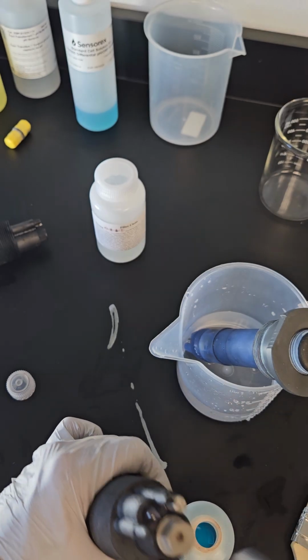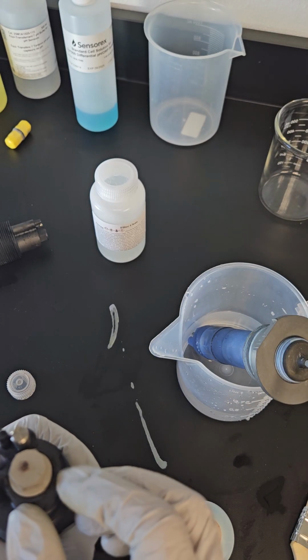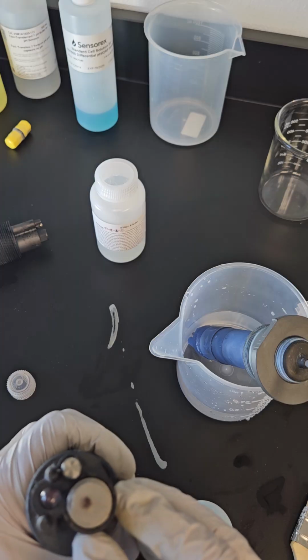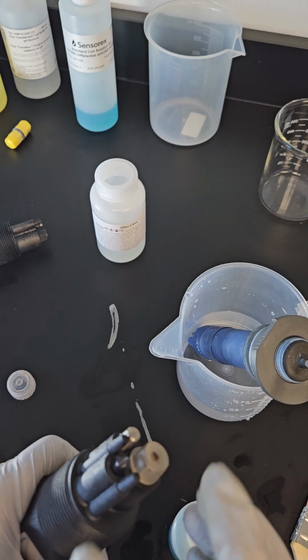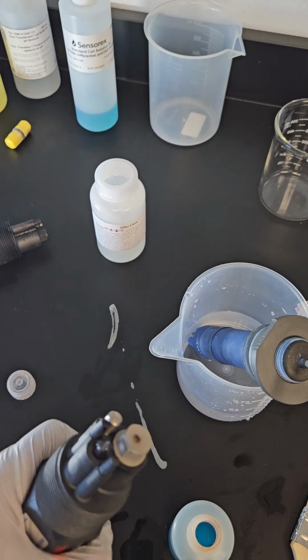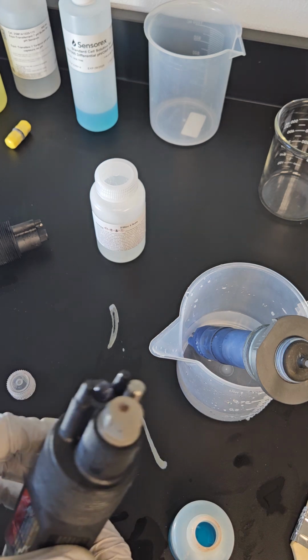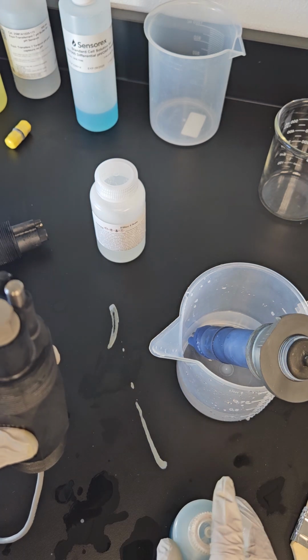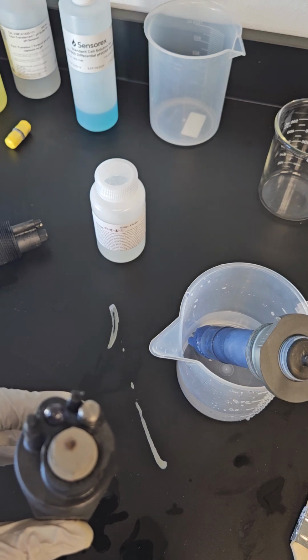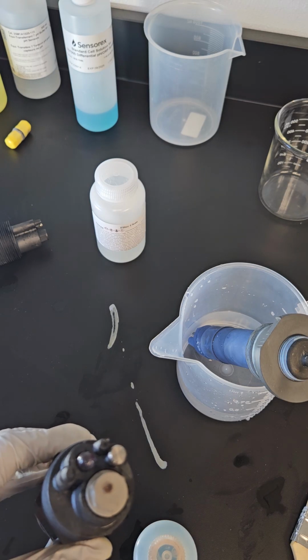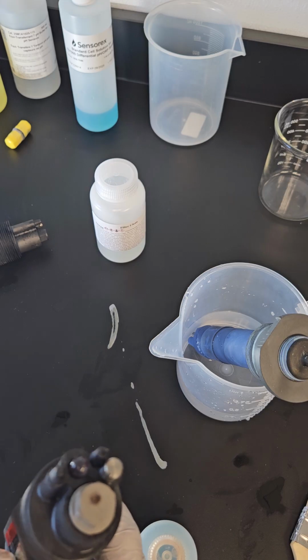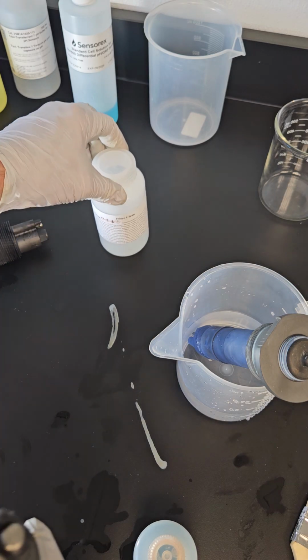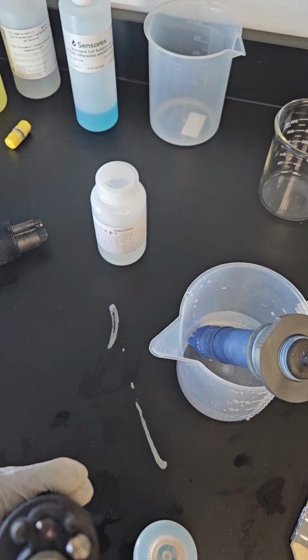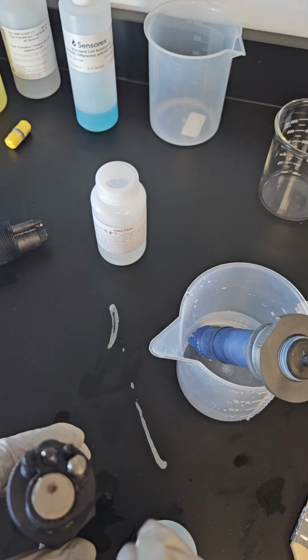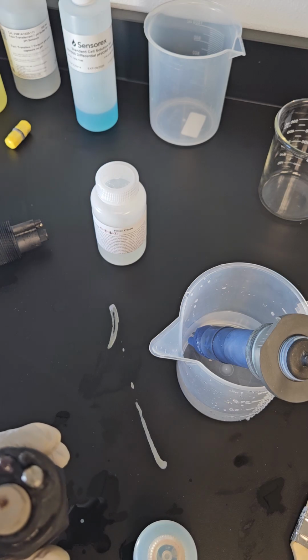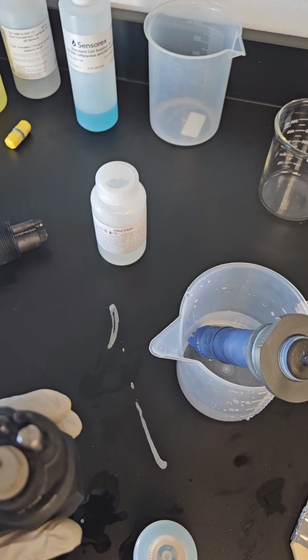It should be one toward the top and one a little bit further in the bottom. Those gaskets will seal plenty. You don't have to over tighten this at all. They're plastic threads, otherwise they're going to break. And again, keep away from the bulb; you don't want to hit that with anything, otherwise it'll break. So that's how you replace the cell reference solution, it's called. Refreshing the reference solution, acid washing it, and cleaning it first with the filter clean is really a deep clean. Even if you still use the same old salt bridge, just giving it fresh solution, a good cleaning, a good acid wash, a lot of times they'll get these probes running smoothly again.